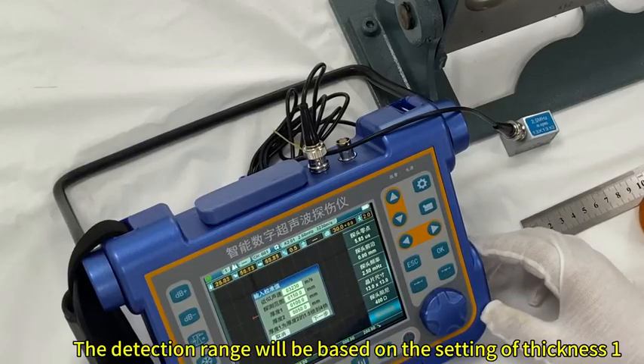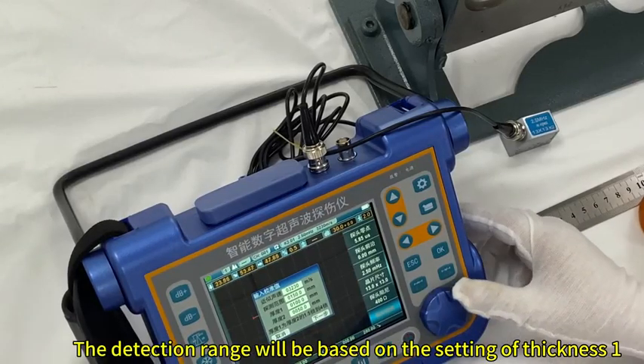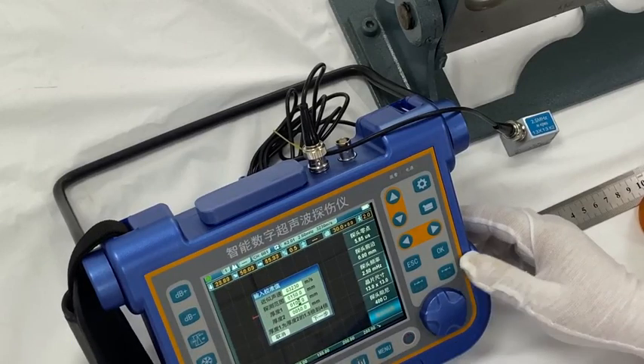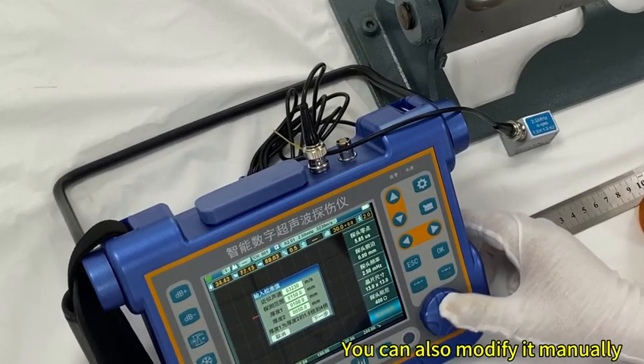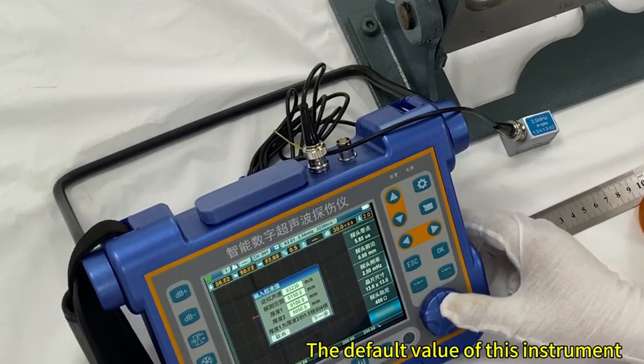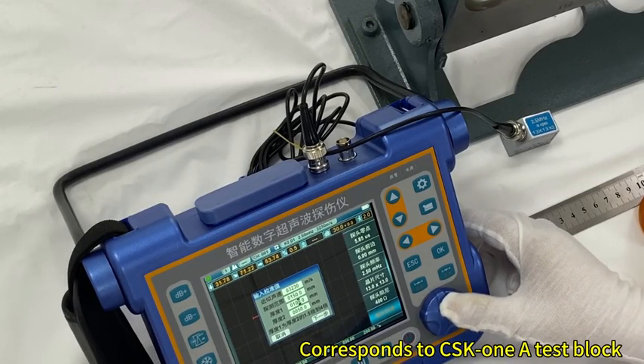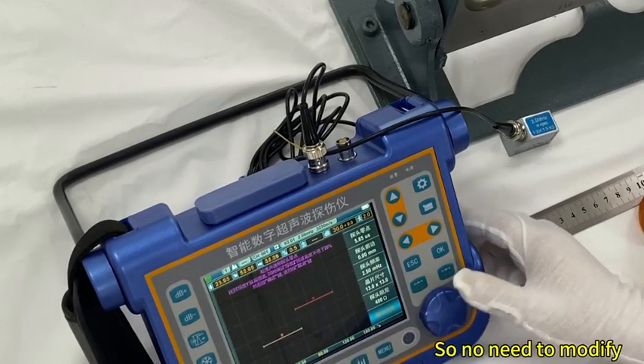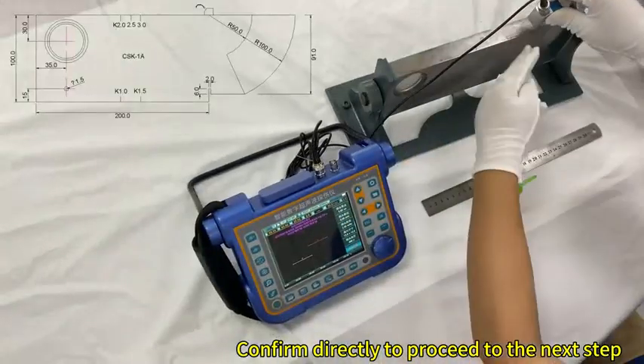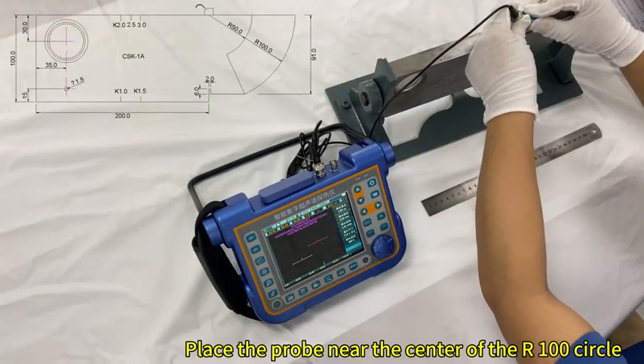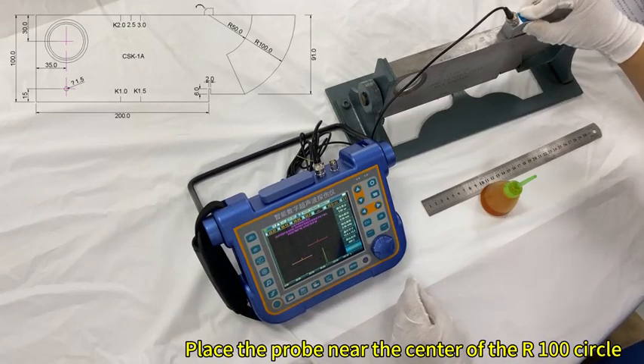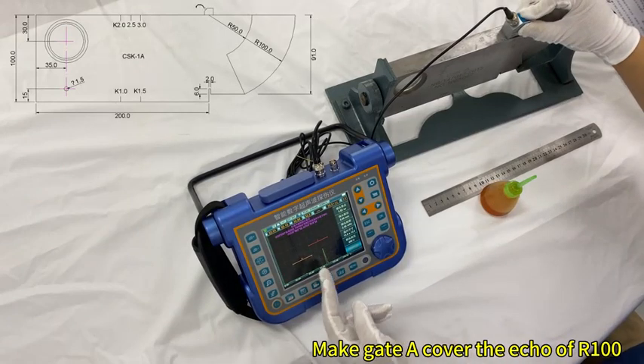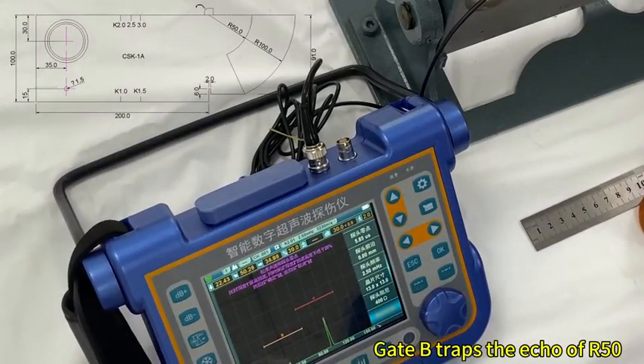The detection range will automatically change based on the setting of thickness 1. You can also modify it manually. The default value of this instrument corresponds to the CSK1 test block, so no need to modify. Confirm directly to proceed to the next step. Place the probe near the center of the R100 circle. Make it cover the echo of R100. Gate B traps the echo of R50.